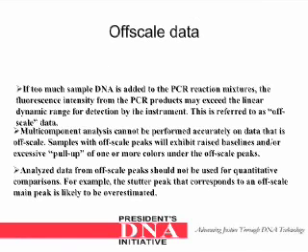Off-scale data: if too much sample DNA is added to the PCR reaction mixtures, the fluorescence intensity from the PCR products may exceed the linear dynamic range for detection by the instrument — this is referred to as off-scale data. Multi-component analysis cannot be performed accurately on data that is off-scale. Samples with off-scale peaks will exhibit raised baselines and/or excessive pull-up of one or more colors. Analyzed data from off-scale peaks should not be used for quantitative comparisons; for example, the stutter peak that corresponds to an off-scale main peak is likely to be overestimated.